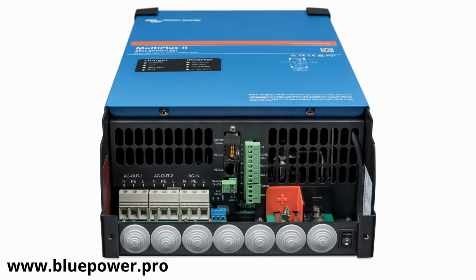Yes. What's currently the max load in the AC out? AC out 2, so that's going to depend on the contactor rating. If you have a look at the part number or on the unit itself, it's going to be a 48 3000 35-32 for this instance, or -50 for 5 kVA or -100 for the bigger units. So that's the maximum AC transfer capacity of the built-in contactor. So you can theoretically run the maximum capacity of that contactor. So with this on the 3 kVA, it's 32 amps.